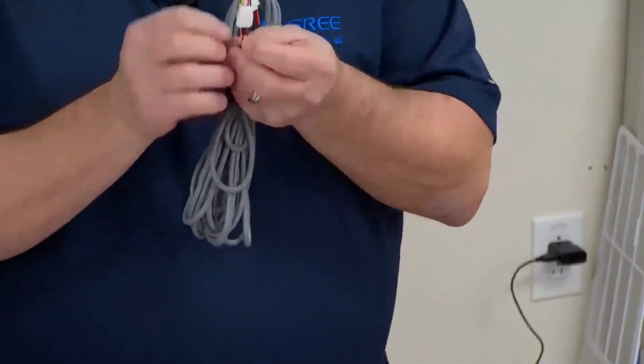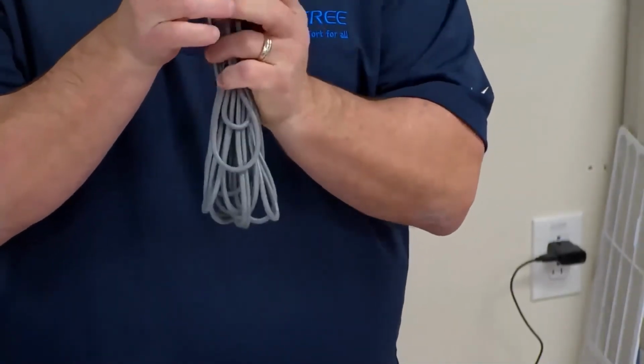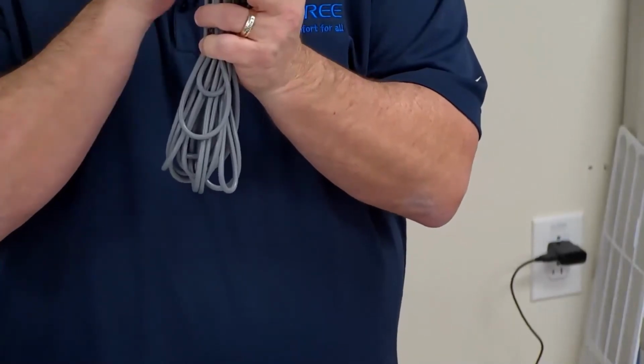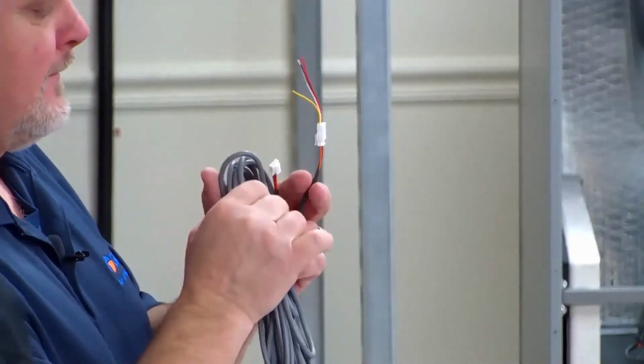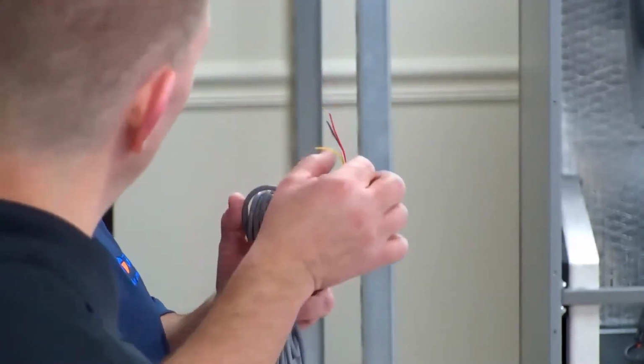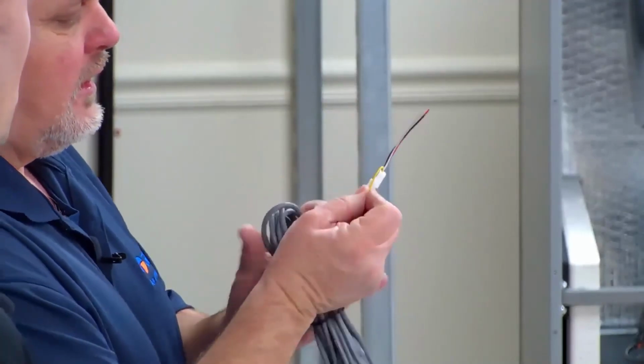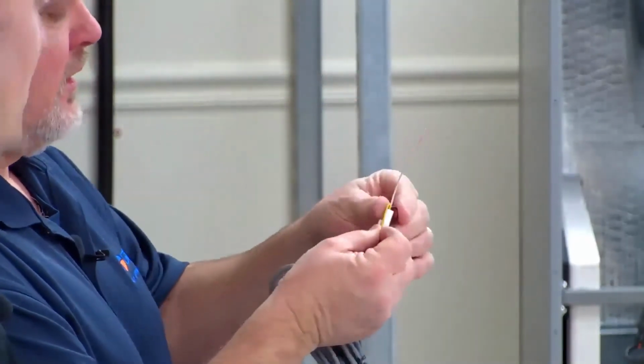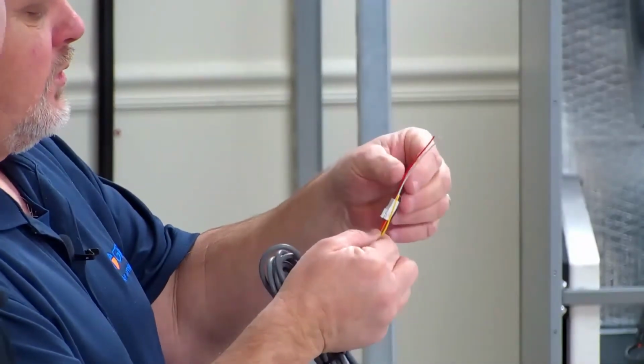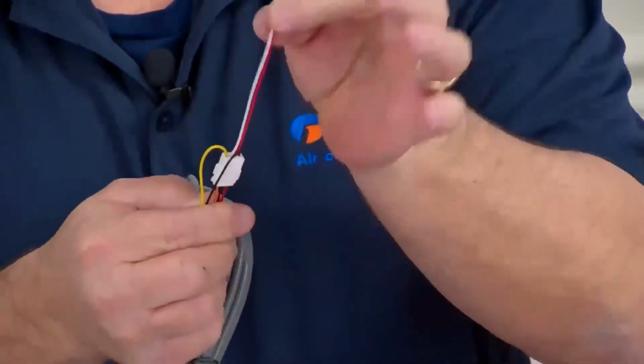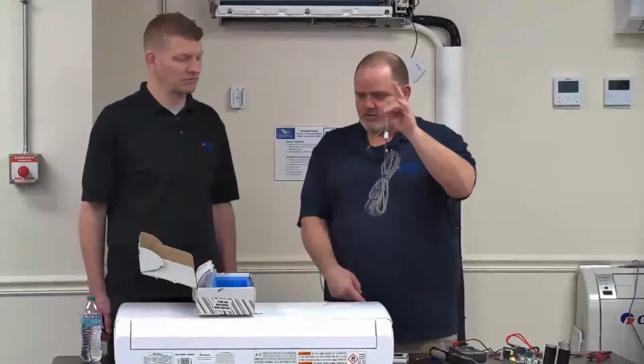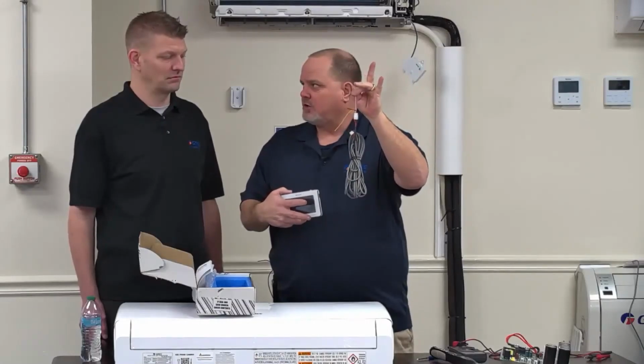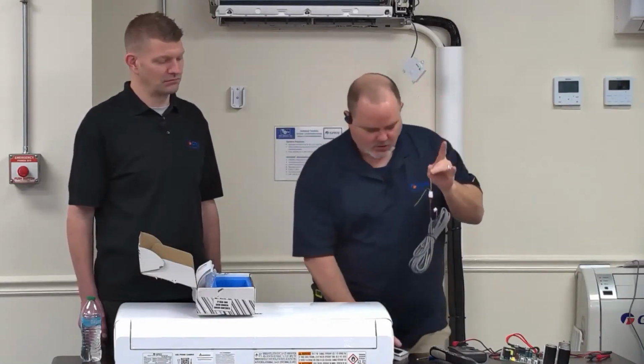Red and black on GREE's plug, red and black of this plug is D1 and D2. Brown and orange is power supply. So the two center ones is what we want to use. So if I put this little adapter on here, again, it's not color matched. The two center wires is all you want to use. I went from red and black to red and white. Then I can take that red and white wire and hook it to D1 and D2 anywhere in the system, as long as I have the portable power supply hooked up to the service tool. The portable power supply will power the tool. This will give you your communication into it. I can hook up anywhere on the system.